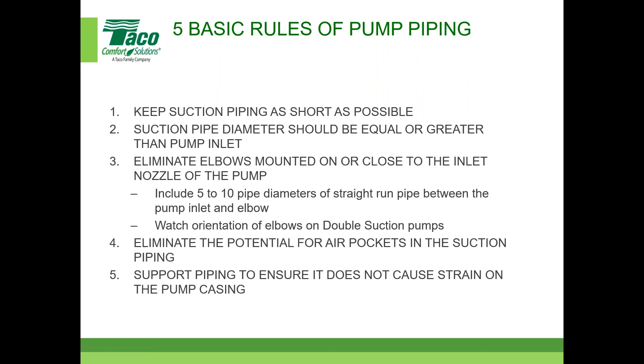You want the flat at the top. Just keep that in mind. And then air pockets, right? Sometimes you go to a job site and you'll see an up and down right before the pump. You're just asking for trouble there. Air into the system is going to cause issues. And then support the piping to ensure it does not cause strain on the pump casing. So, other things to consider there.